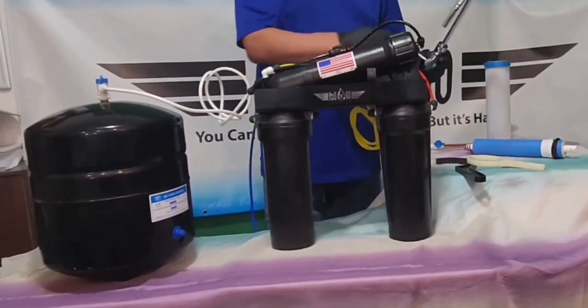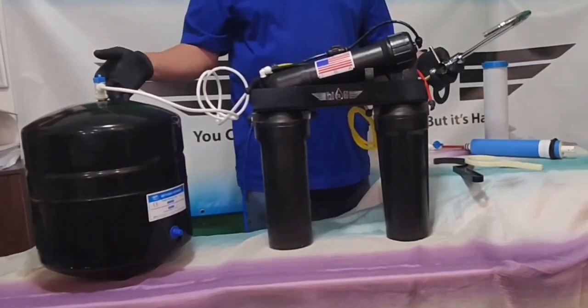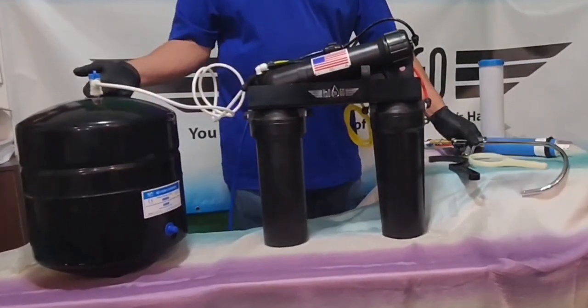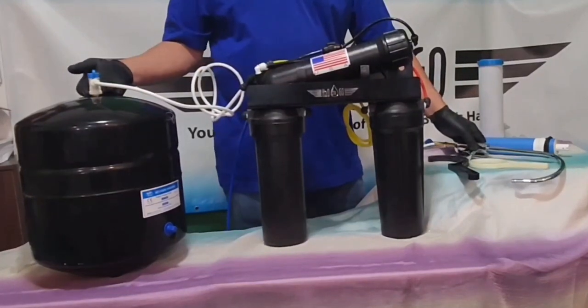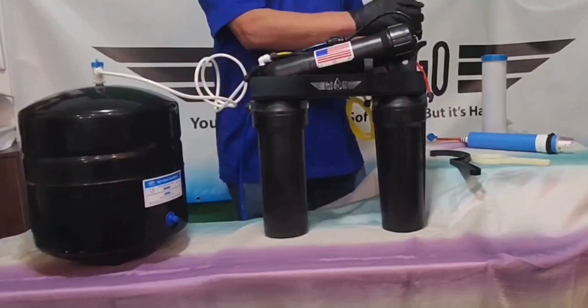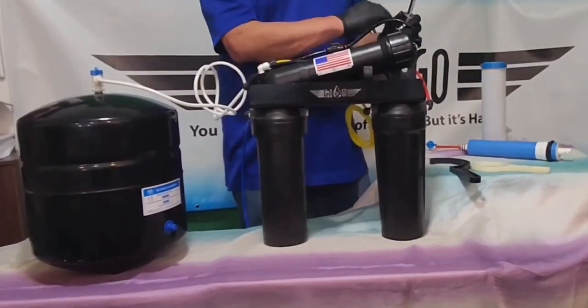you drain your tank. It will take about four to five minutes. After it's drained, you shut it off. You let it fill back up, which will take about 45 minutes to an hour and a half. Drain it again. After that, you're ready to go.